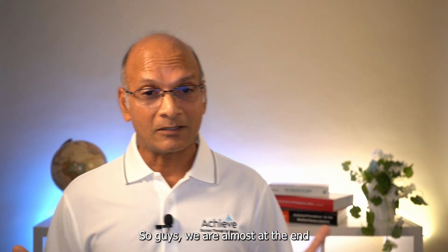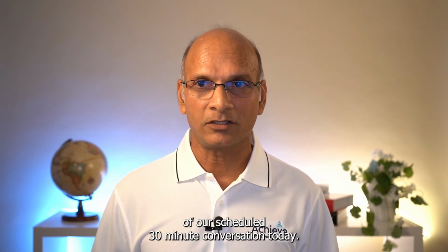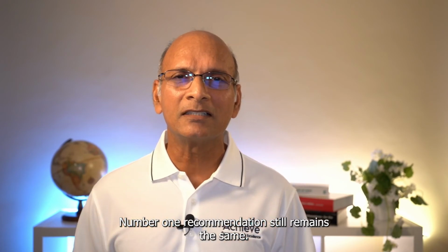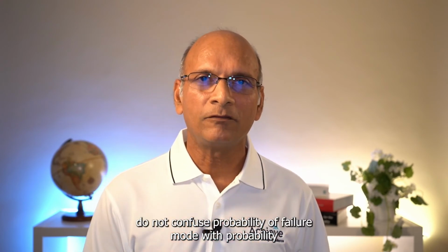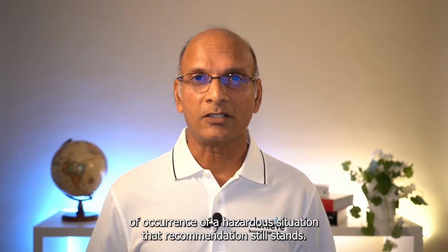So guys, we are almost at the end of our scheduled 30-minute conversation today. So let me summarize what we talked about today. Number one recommendation still remains the same. Do not mix hazard harm analysis in your FMEA. Do not confuse probability of a failure mode with probability of occurrence of a hazardous situation.